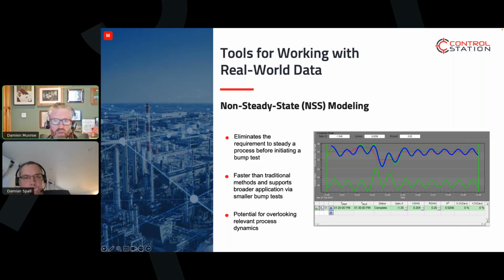We have a unique feature with our tool called non-steady state. You can see the red set point. The lower green line is our output, and the upper green line is our process variable. That blue line is then our process model, our gain, time constant, and dead time. If you move in, or if you've got younger eyes than me, you'll see down the bottom there a gain, time constant, and dead time value, which is that process model that you can define.